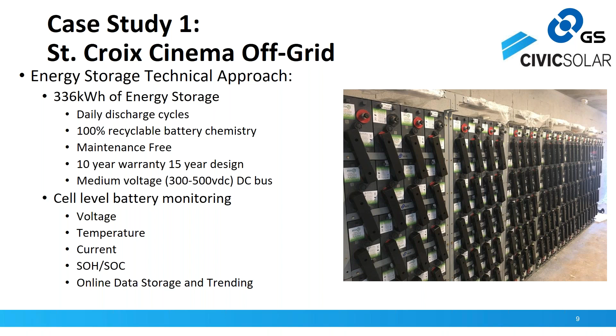We used a medium voltage, so we strung these 2-volt cells in series to create a higher voltage DC bus that would match the solar bus. Everything went into a multi-port ideal power inverter system handling both the PV and the batteries, with a tie-in on the AC side for the generators, all controlled by a field site controller we custom programmed to manage operations at the site. On the battery side, we had comprehensive stats being pulled off of every cell of the system.